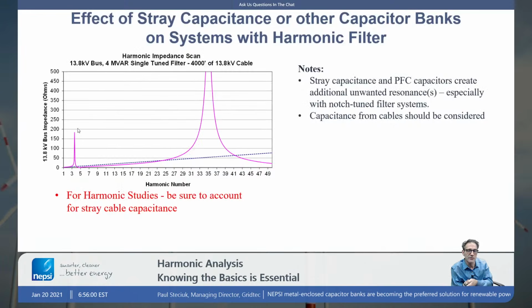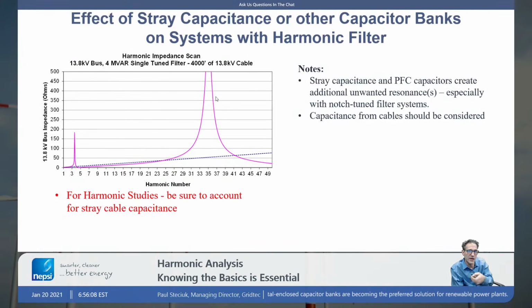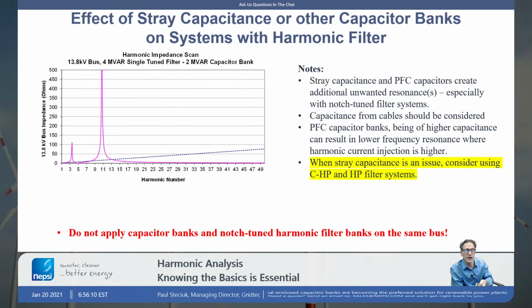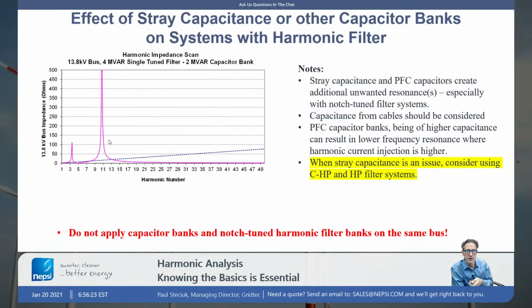This resonance is not a concern because I put in a fifth filter. It pushed that resonance down below. But this one up here is of concern. It could be caused by cable capacitance or because somebody added capacitors to a network. This is an example where somebody put some power factor correction capacitors in the network with a tuned harmonic filter. And here you can see we create an 11th resonance. So because you add a filter to the network, it does not mean you can add a capacitor to that same network.